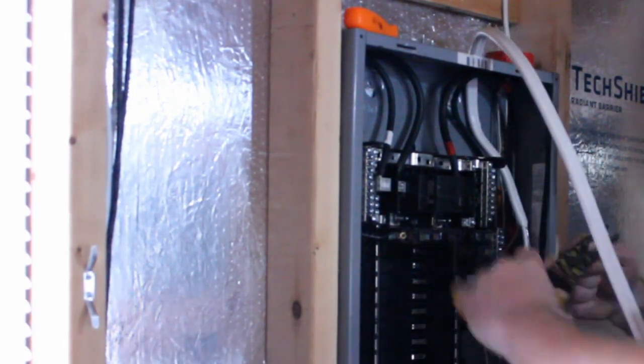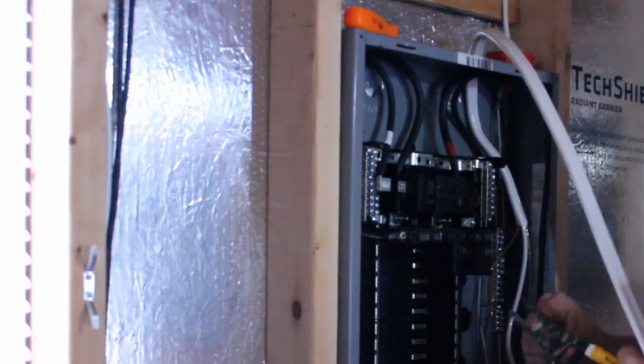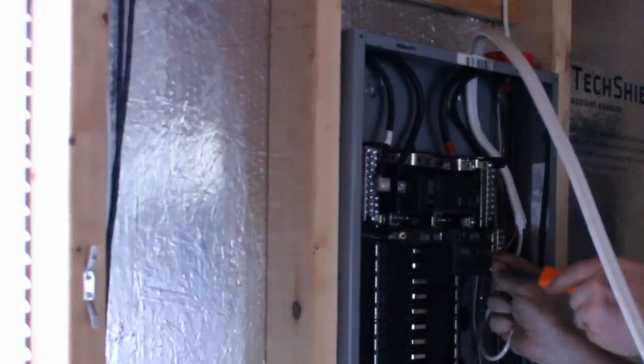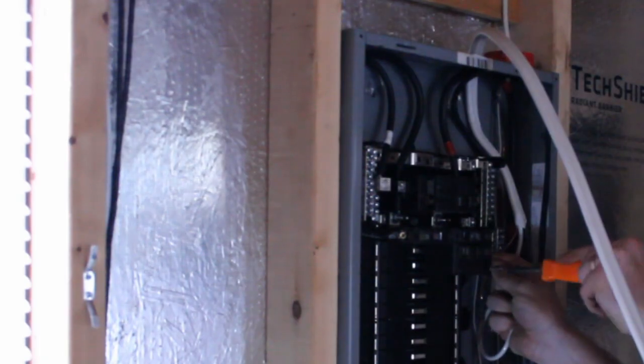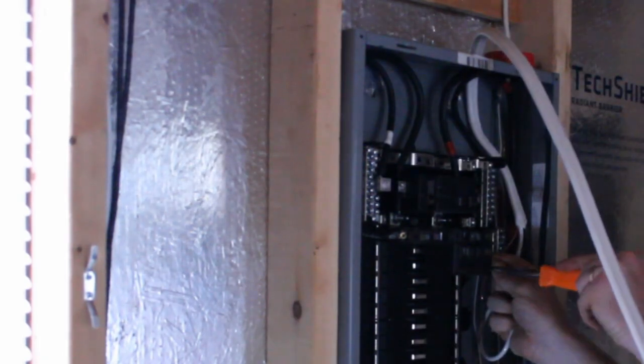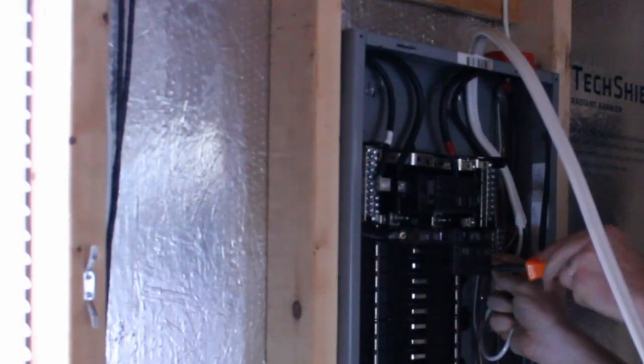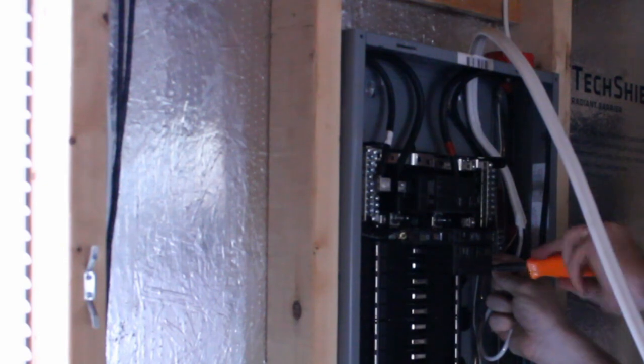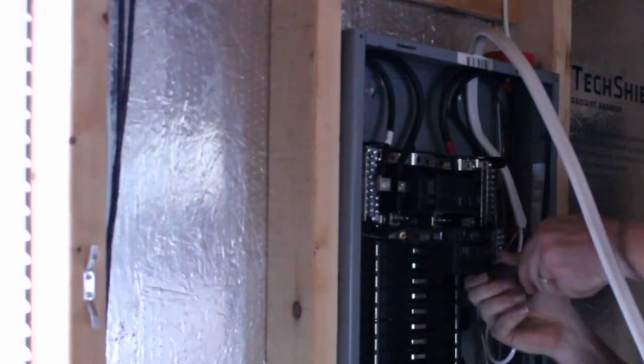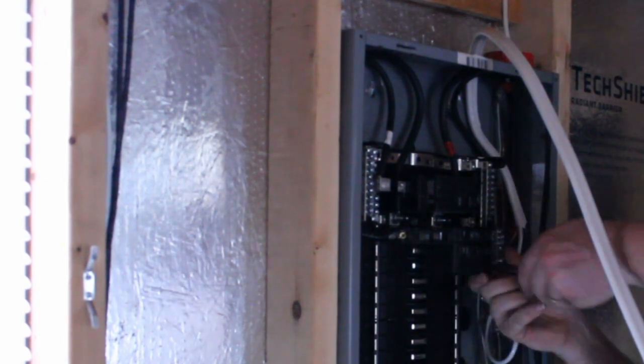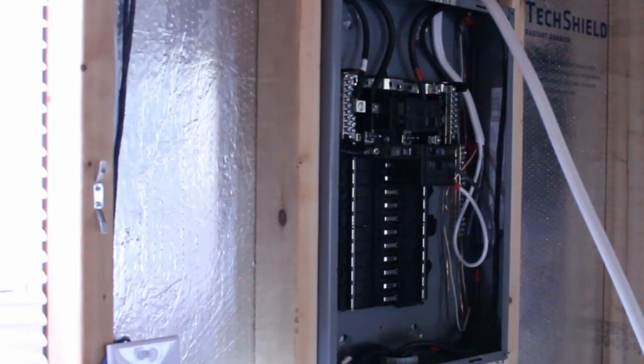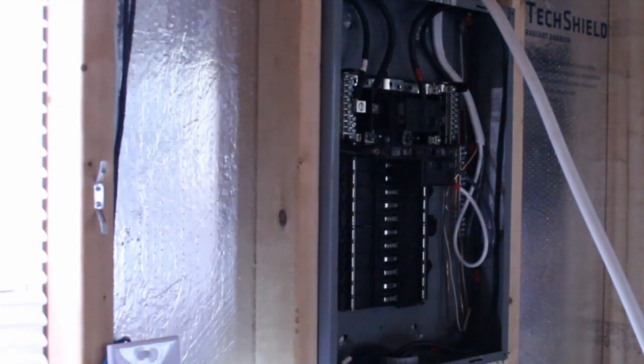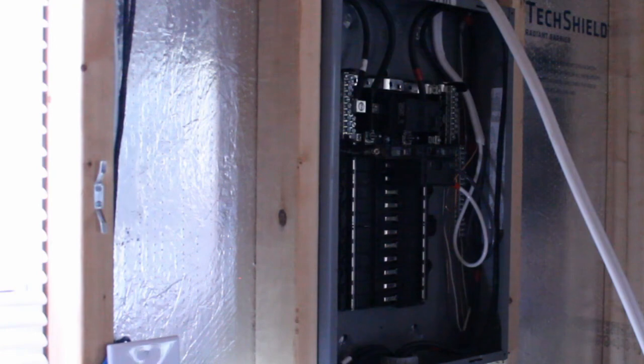Now, since this is a two-pole breaker, I need to connect my two conductor wires from the cable to the breaker. I wired in black and marked the white cable with red tape to signify it's carrying a hot phase and isn't a neutral wire that white normally is used for.